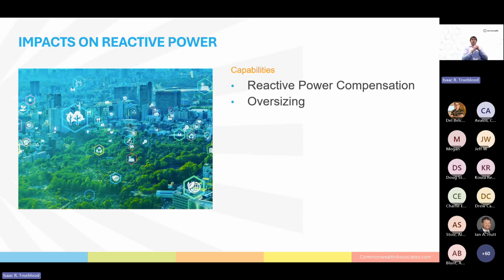Another way to achieve reactive power requirements for inverter-based DERs specifically is to simply oversize them. A 100 megawatt site that only has 100 MVA worth of inverters will be unable to reach that reactive power requirement while maintaining the real power output. By oversizing the inverters, usually 20% is a good rule of thumb, a 100 megawatt site with 120 MVA of inverters can provide the required MVARs without the need for adding capacitors or reactors.